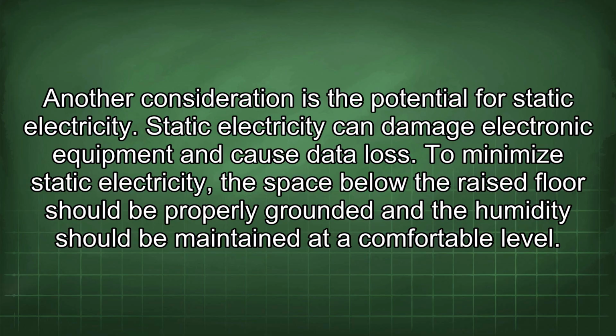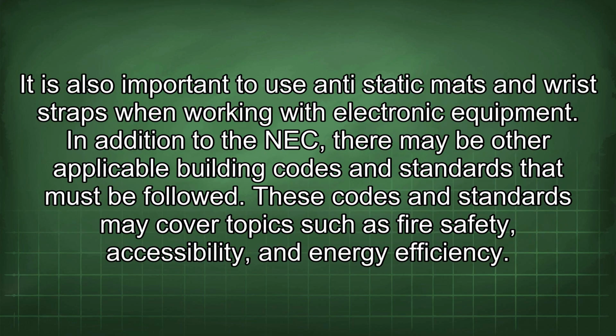Another consideration is the potential for static electricity. Static electricity can damage electronic equipment and cause data loss. To minimize static electricity, the space below the raised floor should be properly grounded and the humidity should be maintained at a comfortable level. It is also important to use anti-static mats and wrist straps when working with electronic equipment.